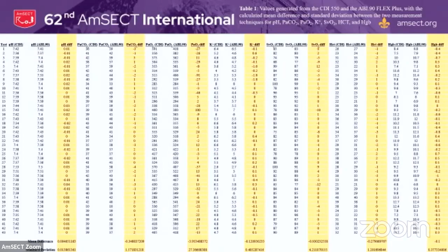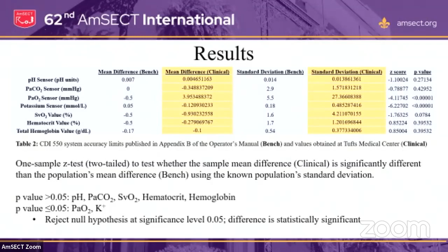And I compared, so bench was the published accuracy limits from the simulated use. The clinical was my result. I did a side-by-side and obtained some p-values, and I was learning which sample test to use. I arrived at a one-sample z-test to compare the two, given that they provided the standard deviation for their tests as well. The only two parameters which had a p-value of less than 0.05, which I selected as my significance threshold, were the PaO2 and potassium. According to the manual, they claimed that the PaO2 was minus like 0.5 less than the analyzer, whereas I got 3.95 greater than the analyzer on average.